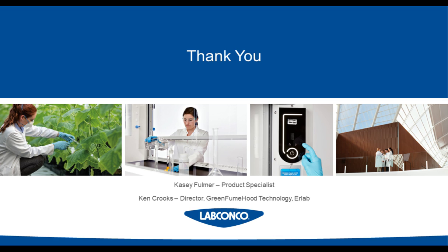And correct, we pass amazingly well without the baffles in the back. The thing to remember here is instead of trying to cram all that air through a 10-inch duct collar somewhat centered in the top of the hood, almost the entire surface of the ceiling of the fume hood is the exhaust port. Those multiple stacks, I showed an example of a 6-footer with 4 filtration columns, those multiple stacks or columns or modules of filtration draw the air up, certainly not laminar flow, not technically anyways, the Reynolds number is not 2000, but in a nearly linear fashion, and we get a much better flow coming in and up and through and out.